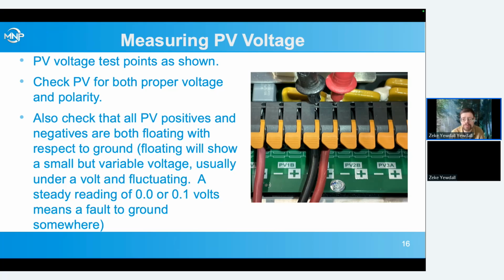Usually what you'll see when you measure from ground to negative is a high initial voltage and then it quickly goes down, but it's not stable at like 0.0. Then you do the same thing with the positive to ground, you'll measure the same thing, maybe 50 to 100 volts initially, and then it quickly goes down to like 0.6 and it's bouncing around a little bit. If you have a nice steady reading, either high voltage or a steady reading of 0.0 or 0.1, that means somewhere there's a connection to ground and you need to find that before turning on the PV switch.